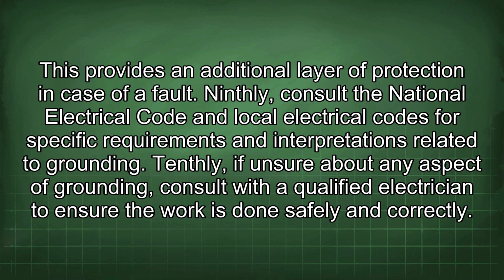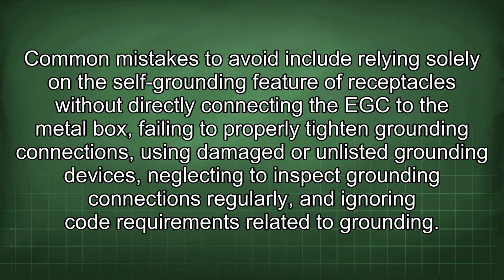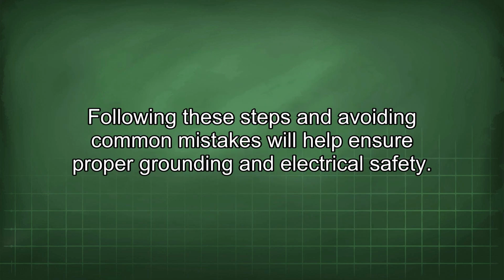and correctly. Common mistakes to avoid include relying solely on the self-grounding feature of receptacles without directly connecting the EGC to the metal box, failing to properly tighten grounding connections, using damaged or unlisted grounding devices, neglecting to inspect grounding connections regularly, and ignoring code requirements related to grounding. Following these steps and avoiding common mistakes will help ensure proper grounding and electrical safety.